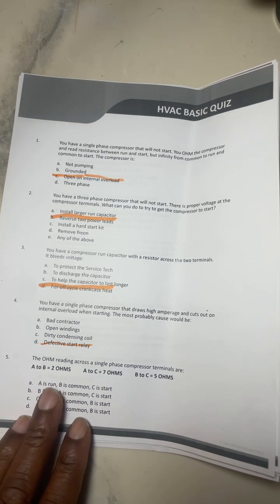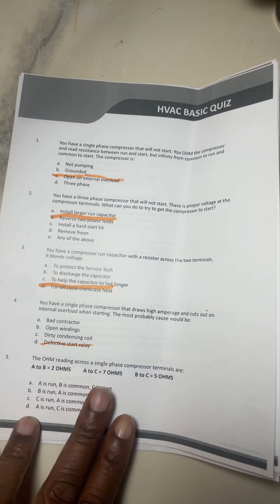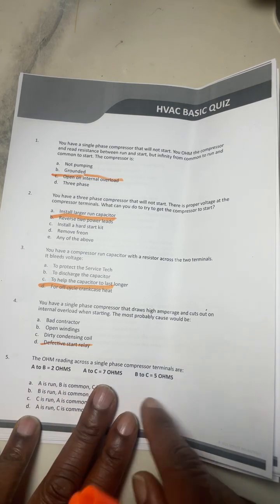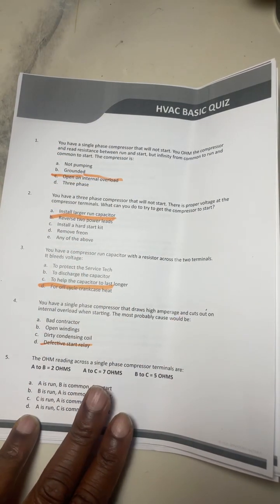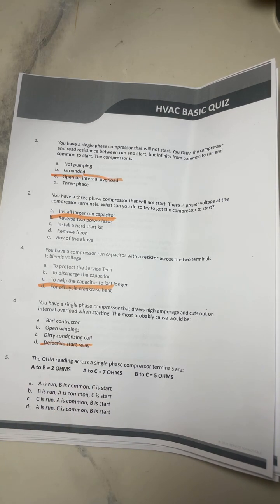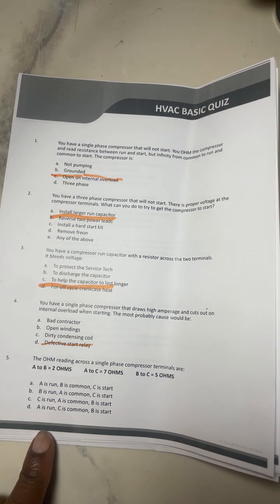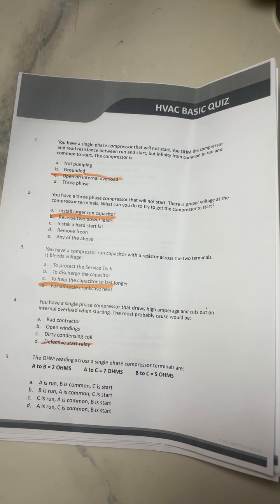Number 5 is the ohm reading across a single phase compressor. And the reason why I can answer the questions is because I do have the answer key next to me. You don't see it, but I see it. So, okay, moving on. The ohm reading across a single phase compressor terminals are A to B equals 2 ohms, A to C equals 7 ohms, and B to C equals 5 ohms. So A is run, B is common, C is start. B is run, A is common, C is start.